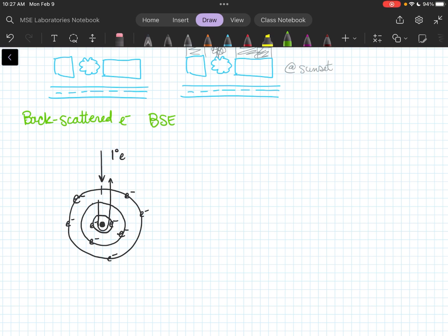I can't stick a detector on top of where the electrons are coming from, because that would block my beam and undo what I'm trying to do. So we build what's called a ring detector. This ring detector goes around where the primary electrons are coming out of the objective aperture. This is how I tend to draw it, as sort of this ring shape.